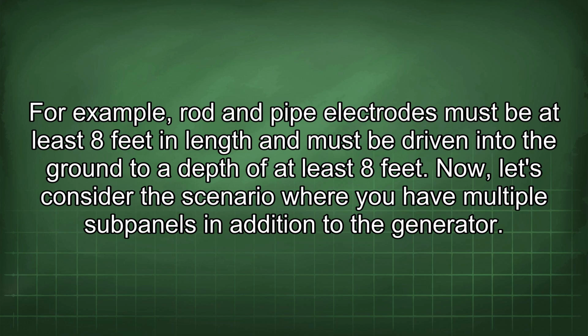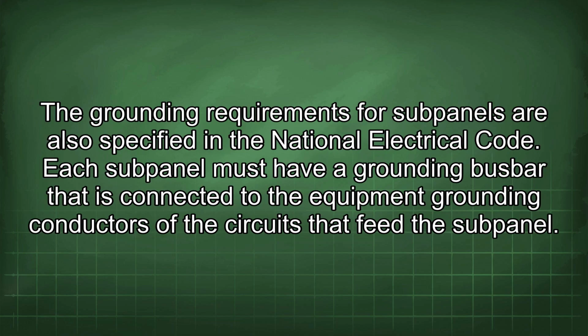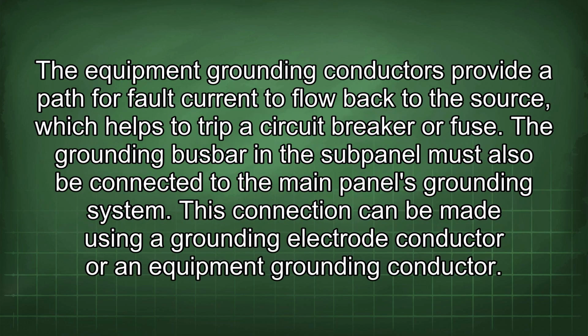Now, let's consider the scenario where you have multiple subpanels in addition to the generator. The grounding requirements for subpanels are also specified in the National Electrical Code. Each subpanel must have a grounding busbar that is connected to the equipment grounding conductors of the circuits that feed the subpanel. The equipment grounding conductors provide a path for fault current to flow back to the source, which helps to trip a circuit breaker or fuse.